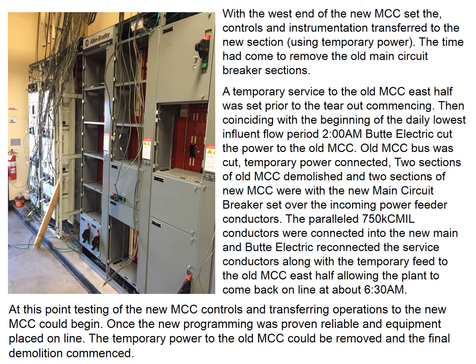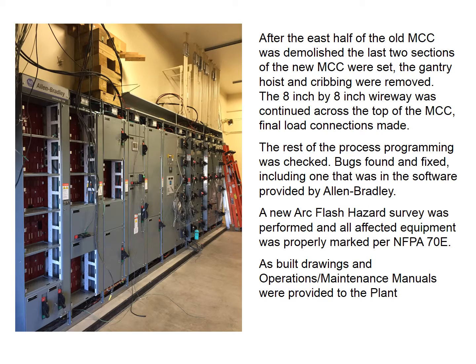At this point, testing of the new MCC controls and transferring operations to the new MCC could begin. Once the programming was proven reliable and equipment placed online, the temporary power to the old MCC could be removed and the final demolition commenced. After the east half of the old MCC was demolished, the last 2 sections of the new MCC were set. The gantry hoist and cribbing were removed. The 8-inch by 8-inch wireway was continued across the top of the MCC and final load connections made.